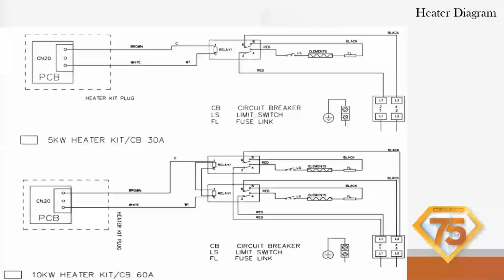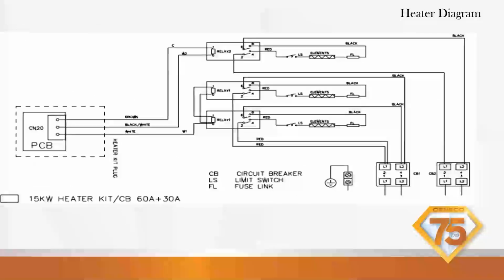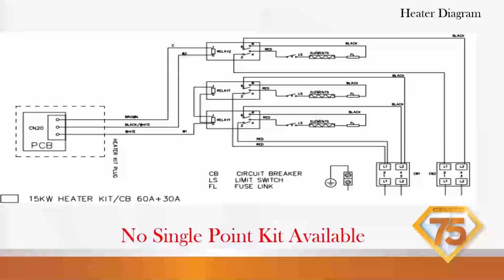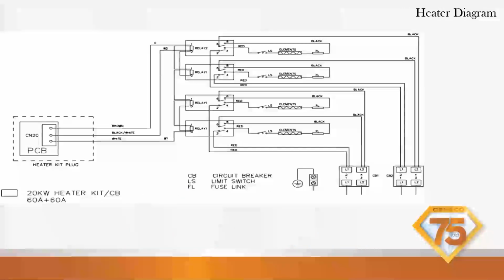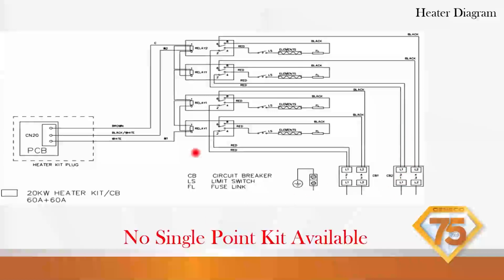Schematics for 5 kW, 10 kW. As you can see, there's 2 elements for the 10. Each one's a 5. 15 kW, got 3 5s in there. Notice a 60 amp and a 30 amp. No single point entry kit available. 20 kW, we got 4 5 kW elements. We got two breakers in here, circuit breaker 1, circuit breaker 2. These will both be listed as 60s. No single point entry kit available for these.